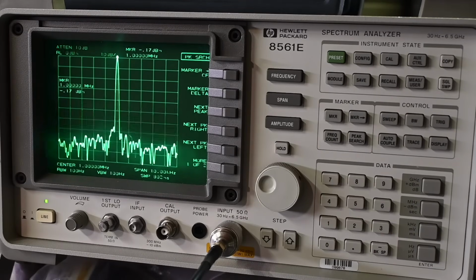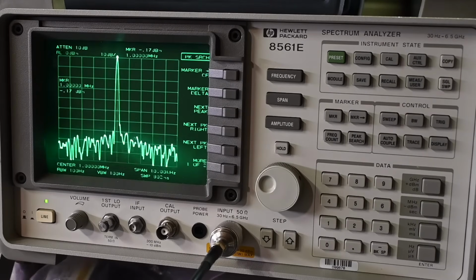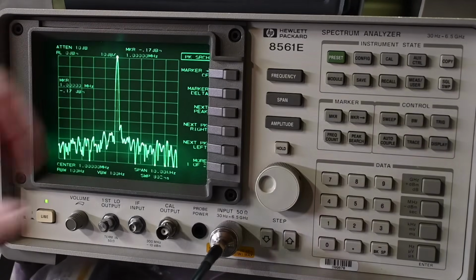So again, you have to use an RF power meter, which I do have, and I'll connect that ultimately to this signal generator and take a look at the actual output just to make sure that it's within spec, because if it says 0 dBm output, it should be right on 0 dBm output or whatever it's set to. But again, this is reasonable because of some slight loss in the cable.